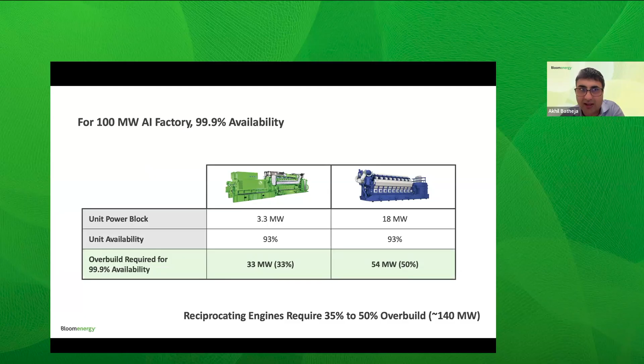With smaller gas engines, slightly less available at about 93%, but because the building block is smaller and the blast radius when something goes wrong is smaller, you need to overbuild less—somewhere between 30 to 50% to hit that 3 nines availability for the 100 megawatt AI factory.